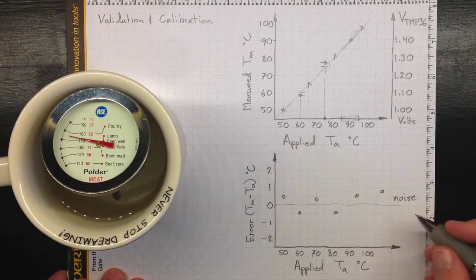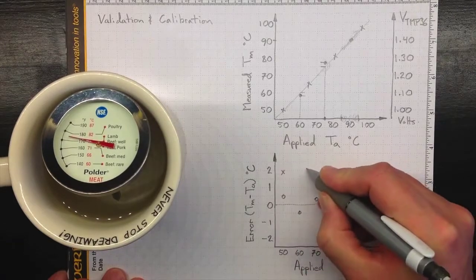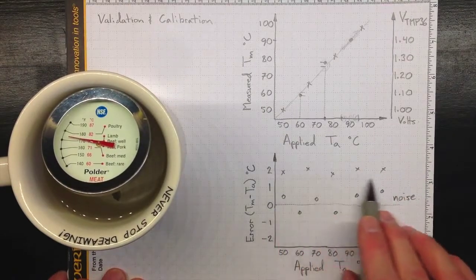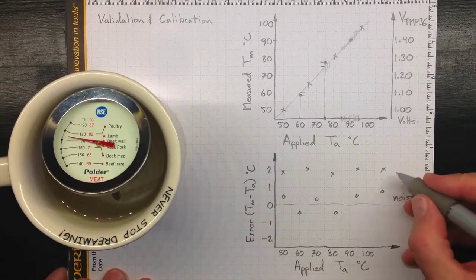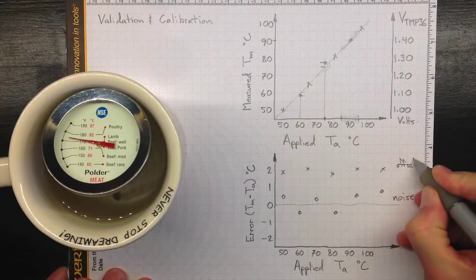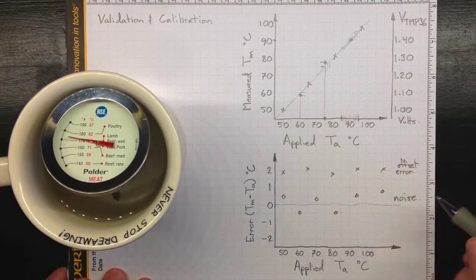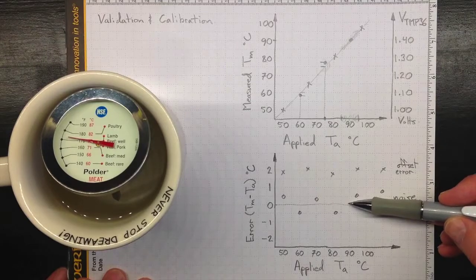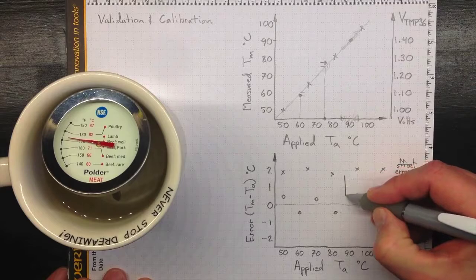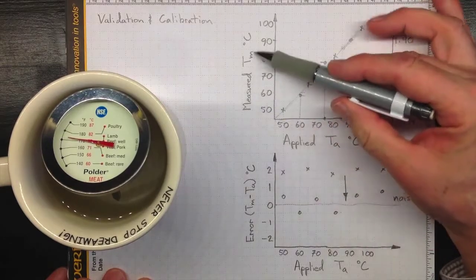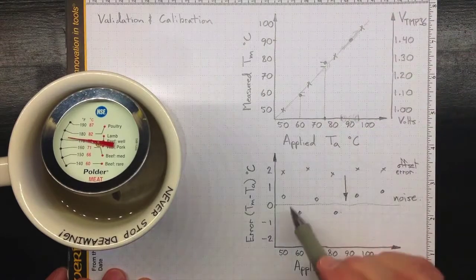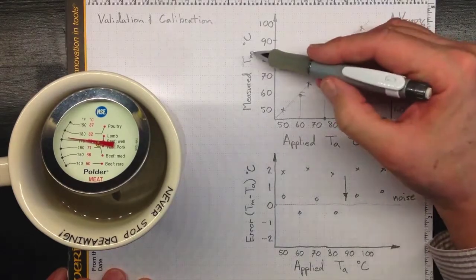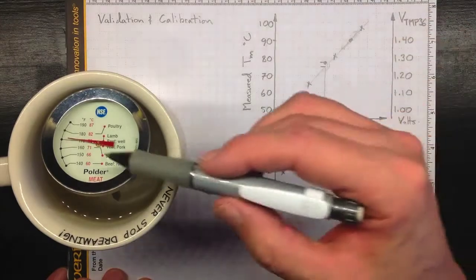On the other hand, we might find that all of our data points were bigger than the value indicated, that we had a positive error on all of these. This tells us that we've got an offset error. All of our measured values are about two degrees higher than the actual value. We could correct for that in calibration. We could move all of these down by taking our measured temperature and subtracting two from it. They'd all wind up back down on this line. That's our calibration process. We can detect what the errors are and adjust how we make an estimate of the actual temperature based on the readout of the dial.